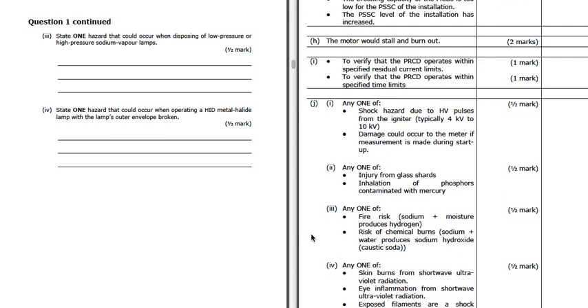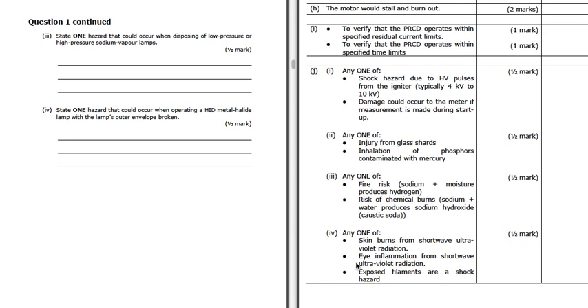So we've got problems with skin burns from the ultraviolet radiation, eye inflammation from shortwave ultraviolet radiation, and we've got exposed filaments that are a shock hazard. So any one of those. So if that outer envelope is broken, we're not going to get the protection that it normally gives us against these ultraviolet radiation, and also there's a shock hazard.